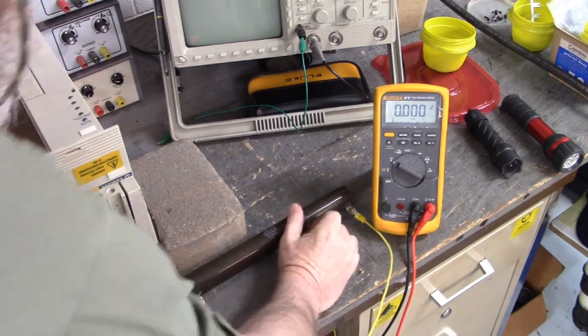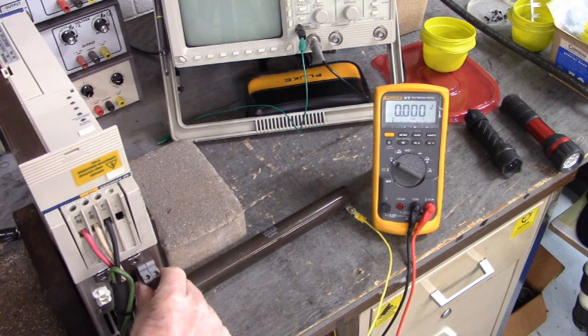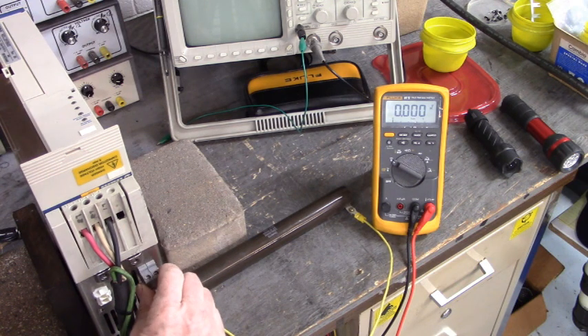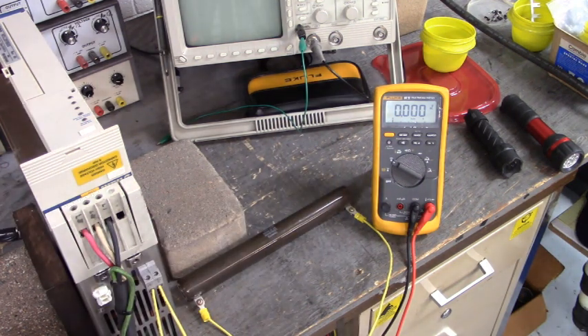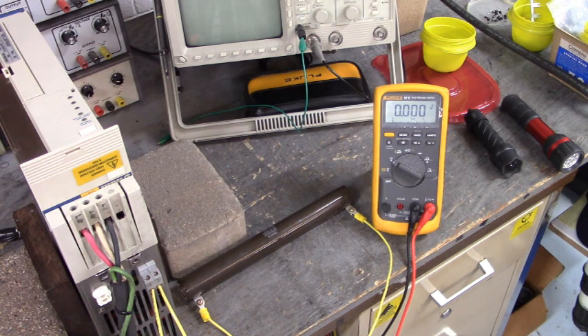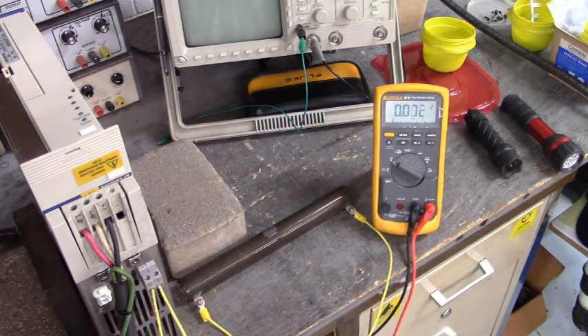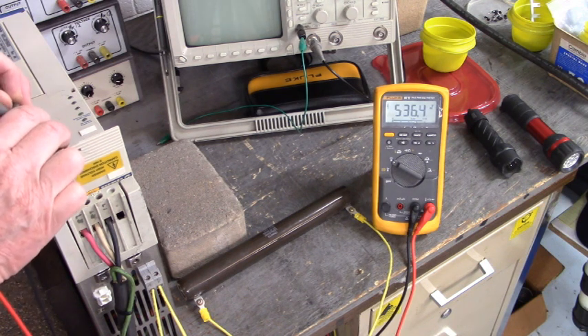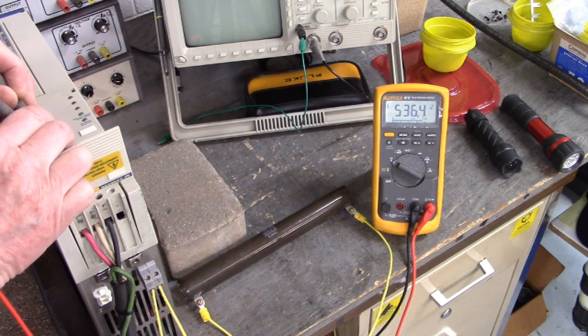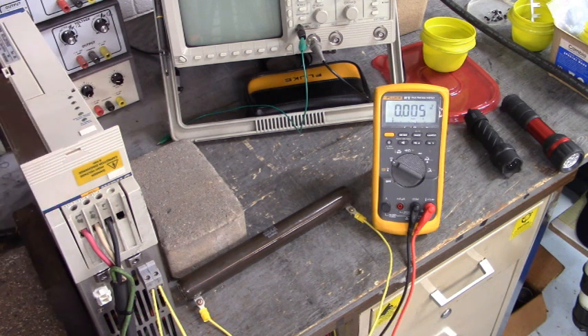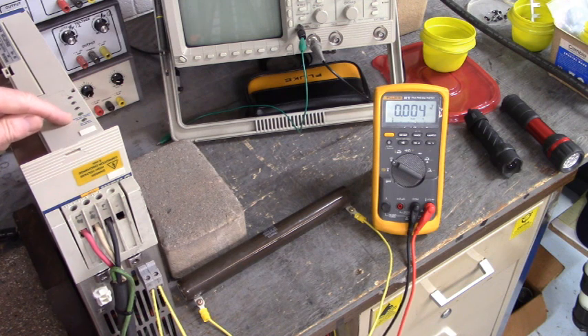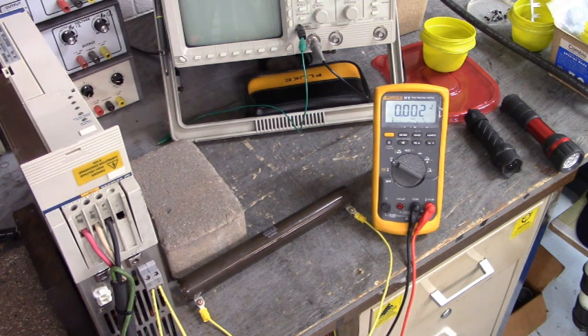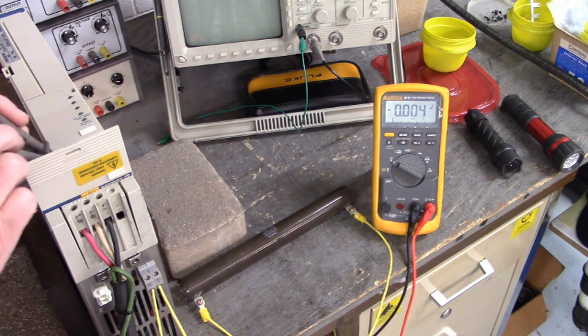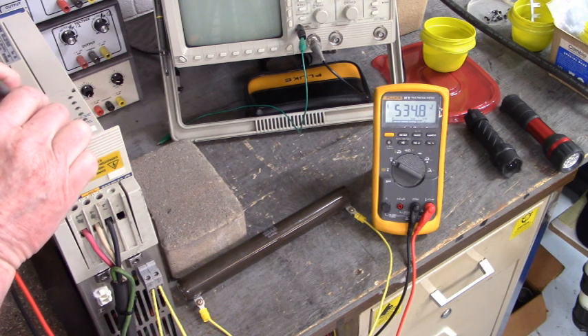Now with the regenerative braking resistor of 25 ohms, 225 watts connected to this gray connector, this is our regenerative braking resistor connection, we'll power everyone up and we'll measure our DC bus voltage out here. Alright, did you hear that contactor energize? We should have a DC bus. There we do. 536.3 volts DC on these terminals right here. And our green power LED is on, as well as our control voltage LED. Both LEDs are on. Good, good. Let's measure that again. 534.8 volts DC.